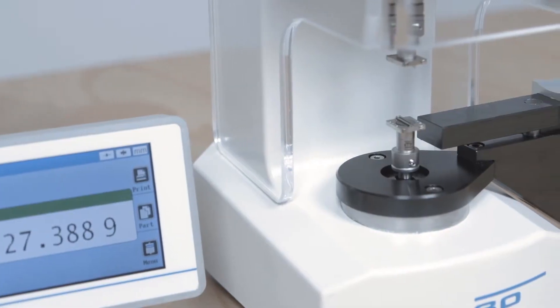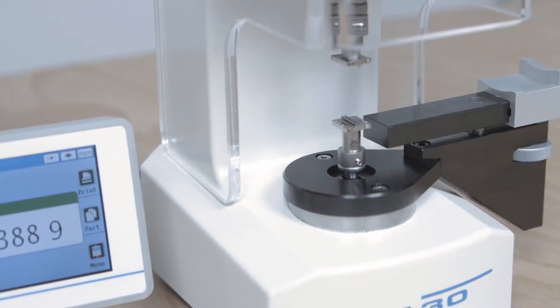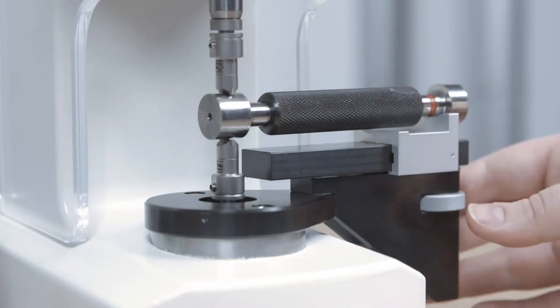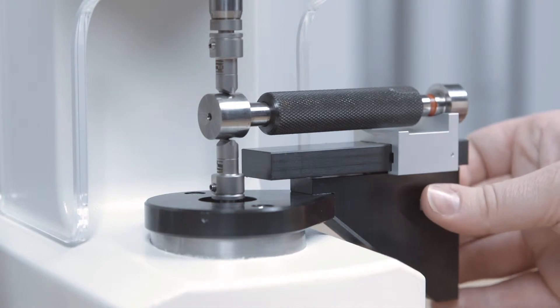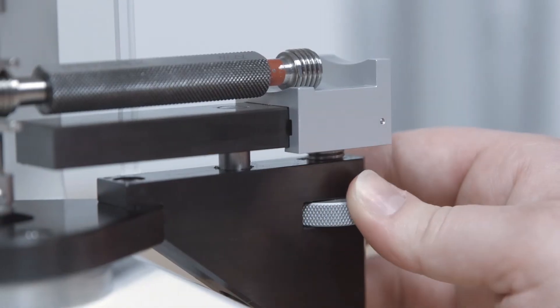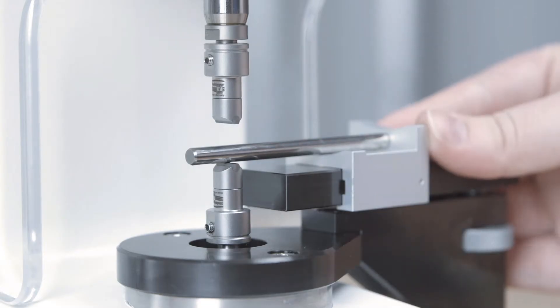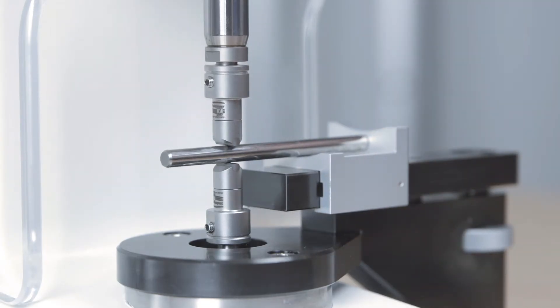Various tabletop versions and supports are available to hold the measurement gauges and these can be changed very quickly. The support for plug and pin gauges offers height adjustment and the corresponding table can be moved in an X and Y direction. This permits a simple and safe alignment of the measuring surfaces.